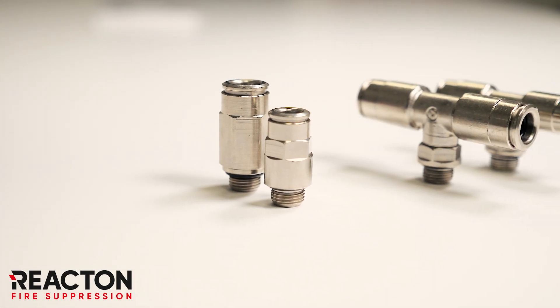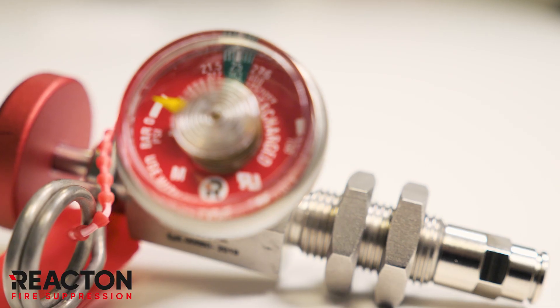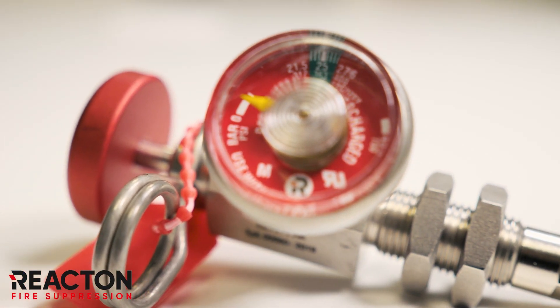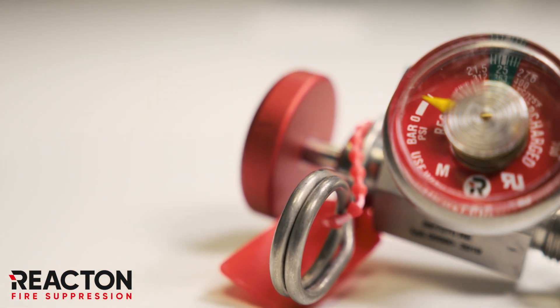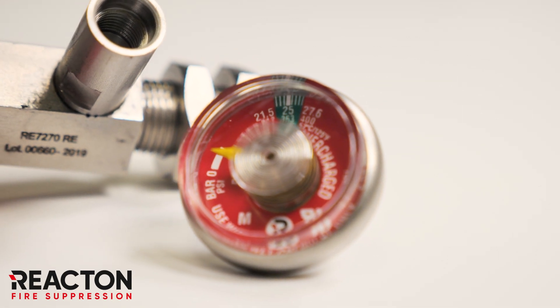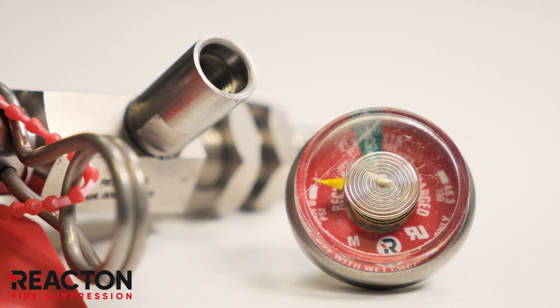This is easily configured with either the 6/4 millimeter or 8/6 millimeter stud or tee connectors. Each actuator allows system pressure status via its UL listed gauge. This gauge can be safely removed on devices even under pressure, allowing safe and secure commissioning of the system.